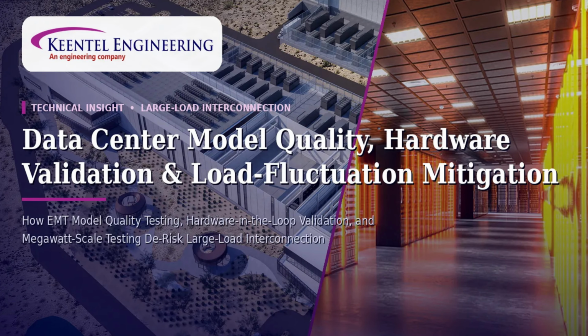Welcome to Keentel Engineering. Today, we're covering data center EMT modeling and large load interconnection because the model is now part of the interconnection agreement. This is about how EMT model quality testing, hardware in the loop validation, and megawatt-scale testing de-risk large load interconnection, and why a bad model can stall gigawatts of load.